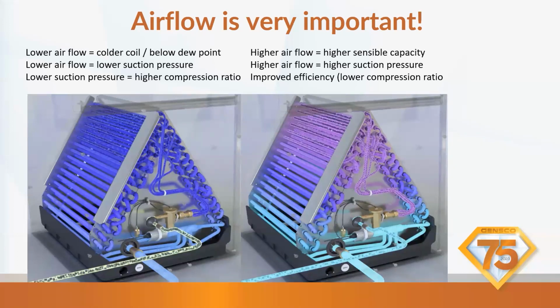This shows you the effects of low charge, airflow. Lower airflow means a colder coil, so you're below dew point. So lower airflow could lead to icing up on the coil too.